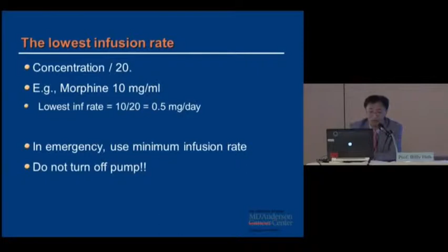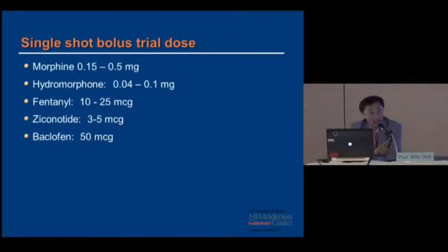Typically, for a single shot trial dose, we use morphine at 0.15 to 0.5 milligram, depending on how opioid tolerant the patient is. Hydromorphone is 0.04 to 0.1 milligram, or 40 to 100 micrograms. Fentanyl is 10 to 25 micrograms. Ziconotide, a calcium channel blocker, is anywhere from 3 to 5 micrograms. Baclofen is typically 50 micrograms—you can go as high as 100 micrograms, but typically they do well, and you can get a lot of information out with only a 50 microgram injection.